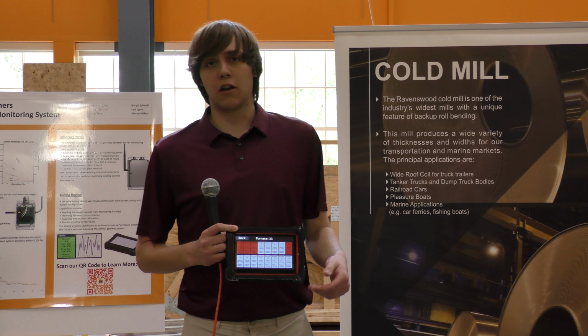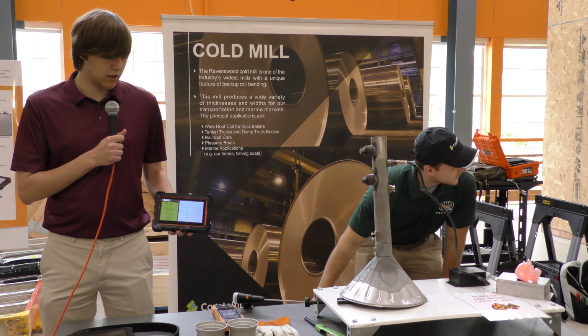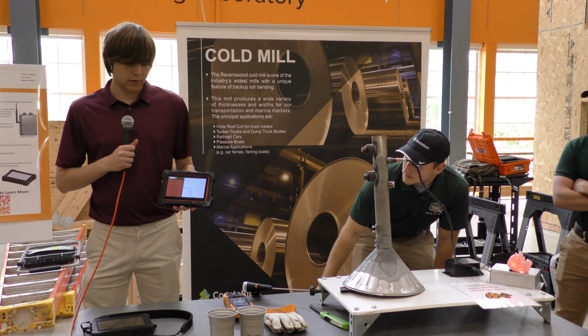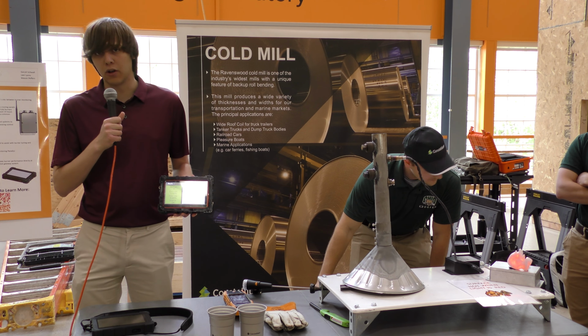This basically tells the operator that if it's red, it needs to be tuned, and we can go through and tune that burner. We can even go one level deeper into a single burner, and that's where we can start to see a trend line and really see how the data is moving. This burner right here is what's connected to the smokestack right now, and we can see that it's at roughly 9% excess O2. If we go and tune this, we can see it gets closer, and you see a color gradient there as you get closer to 3% excess oxygen, which is the goal.